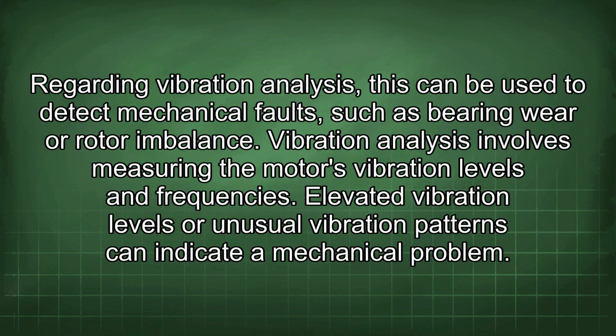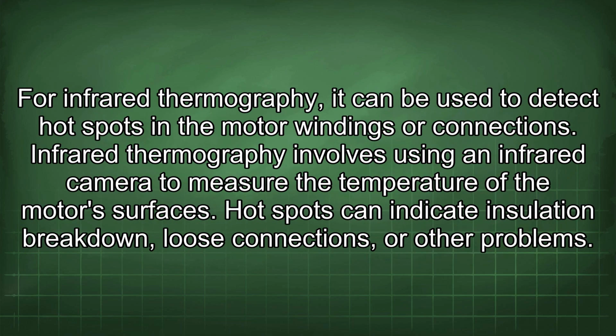Regarding vibration analysis, this can be used to detect mechanical faults such as bearing wear or rotor imbalance. Vibration analysis involves measuring the motor's vibration levels and frequencies. Elevated vibration levels or unusual vibration patterns can indicate a mechanical problem. For infrared thermography, it can be used to detect hot spots in the motor windings or connections. Infrared thermography involves using an infrared camera to measure the temperature of the motor surfaces. Hotspots can indicate insulation breakdown, loose connections, or other problems.